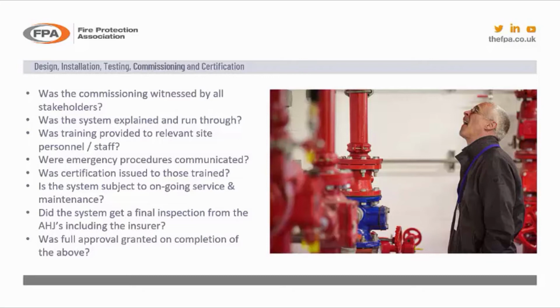Sometimes sprinklers go off, they're knocked, accidental damage. A sprinkler's gone off, the pumps have kicked in. What do we do? Has this been communicated? Has the training been communicated so they know where to go, what to shut down, who to phone, and then how to get the system reinstated? And then once they've done that training, did they provide certification to those on-site staff or those on-site personnel, the engineers on site who are going to do the weekly testing and maybe monthly testing of the sprinkler system, which my colleague Ian Walters will come on to in part 3.